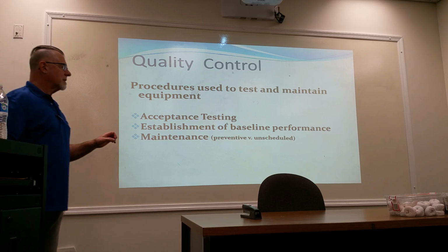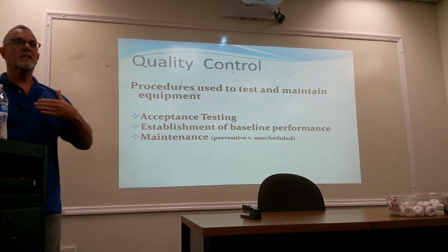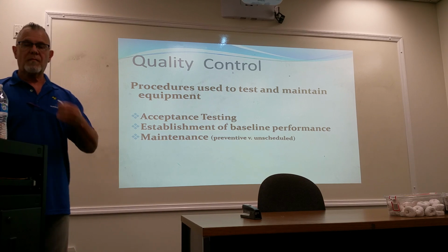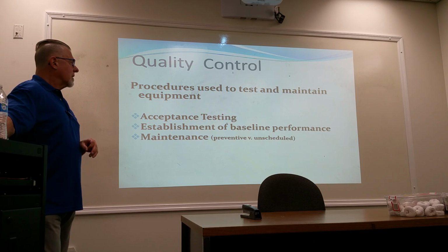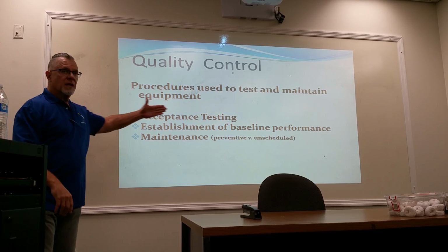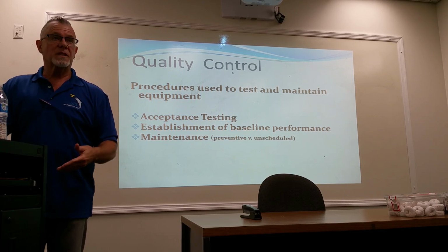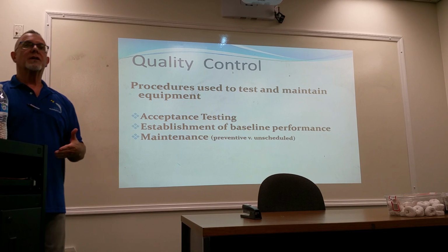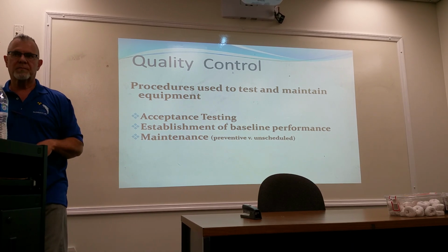And that's usually in the documentation that the federal government requires that they give to owners. Usually there's a quarterly, some equipment is semi-annual, other piece of equipment is annual. The vendor comes in and does their preventive maintenance. If you have an engineer on site in your facility, usually that engineer is the person doing these according to what the manufacturer requires. Okay.